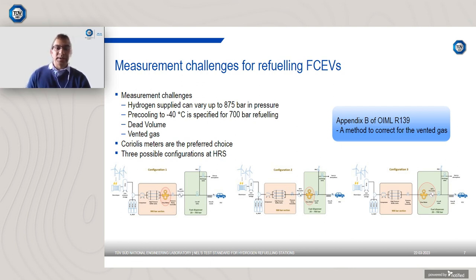Another reason for the billing inaccuracies could be a lesser known effect, which has to do with the pressure and density changes that occur in the dead volume or inventory volume. This is the volume of gas that is between the flow meter and the cutoff valve. Depending on the filling process followed by the current consumer versus the previous customer, if you were to fill a car up with a different pressure, you end up with a different amount of gas that gets trapped within this region. And as a result, you end up with a billing inaccuracy.